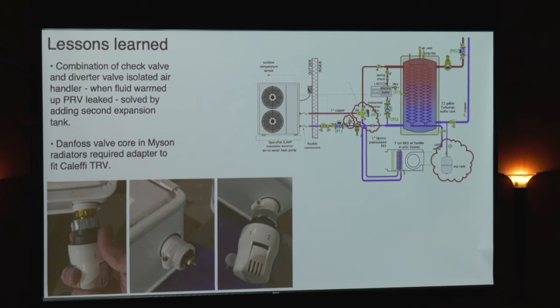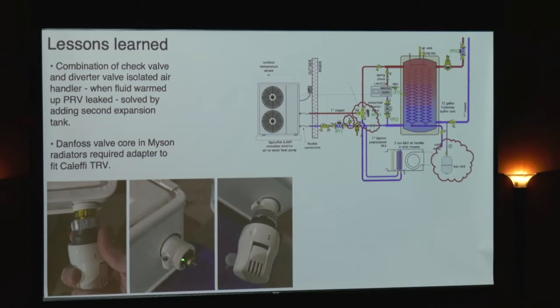Unfortunately, the folks in Italy at Caleffi came up, they had a little adapter, and all it does, here it is, you put it over the valve, it's got a little set screw that holds it in place. It just extends the threads that hold the TRV, and then the TRV threads right onto that. So check if you're working with thermostatic radiator valves, yeah, I guess the default advice, buy the valves and the radiators from the same supplier because they're going to be compatible. If you're shopping around and using different products, make sure you've got compatibility between the TRVs and the valve cores. So those are a couple lessons learned in there. We were able to resolve both of the issues, and the system is working good.